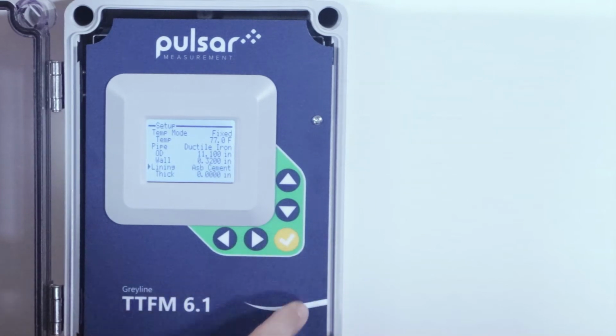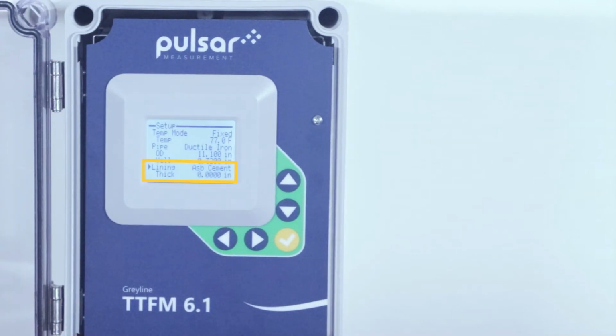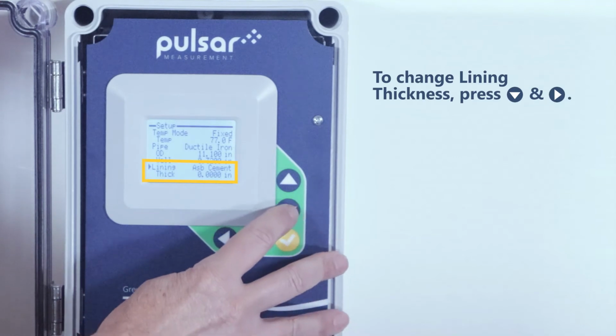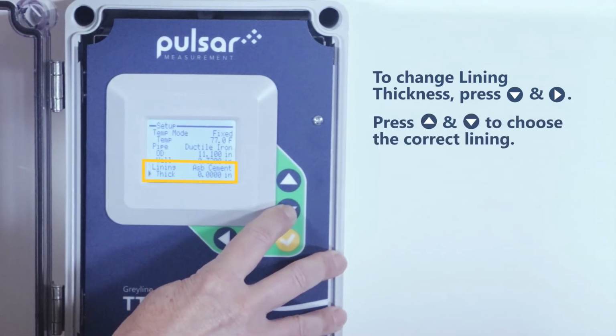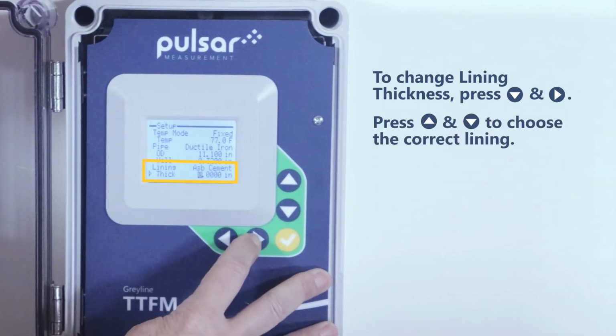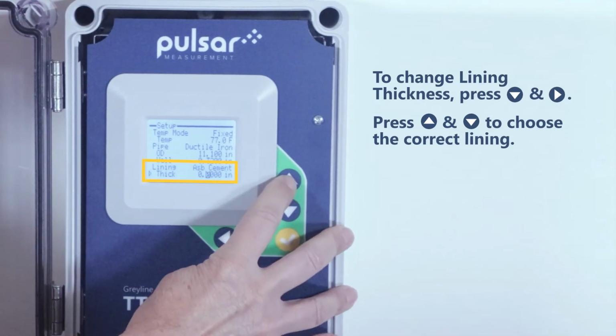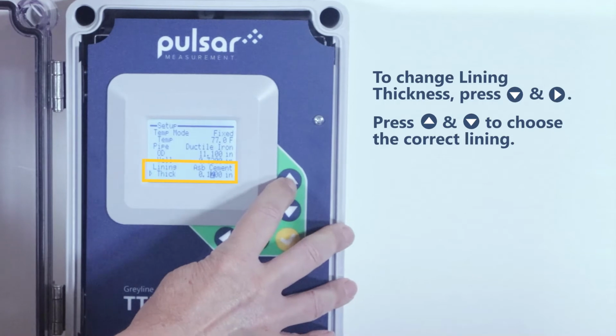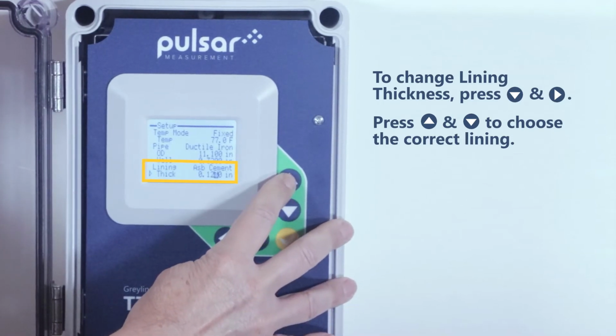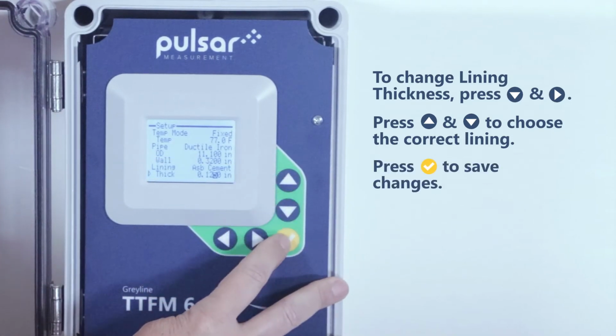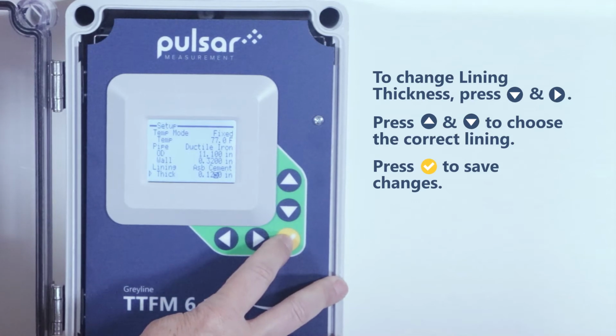A new menu option for lining thickness now appears. According to the pipe charts, this should be set at 0.125 inches. We'll hit the down arrow button, then the right arrow button, and make the change. Remember, check mark to make the change permanent.